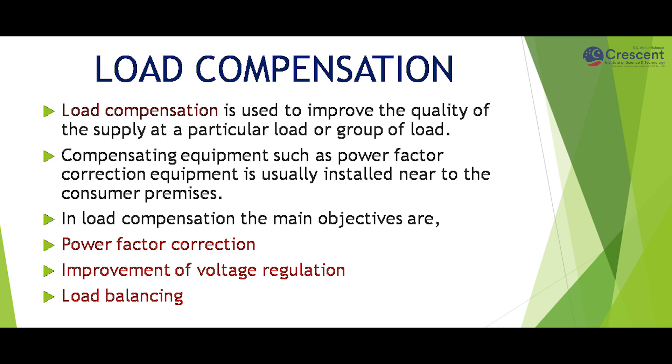What are the main objectives of load compensation? Load compensation must have three main objectives: one is power factor correction, number two is improvement of voltage regulation, and number three is load balancing. The compensating equipment such as power factor correction equipment is usually installed near the consumer.